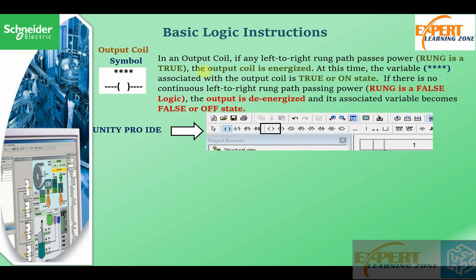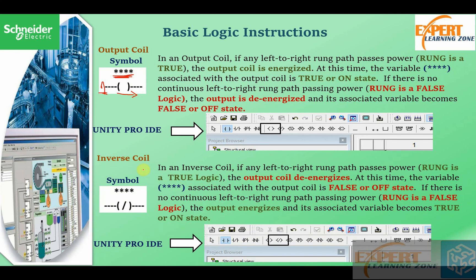The output coil: if any left-to-right rung path passes power — that is when the rung is logic true — the output coil is energized. At this time, the variable associated with the output coil is true or on. If there is no continuous path from left to right, then the output is de-energized and its associated variable becomes false or off.